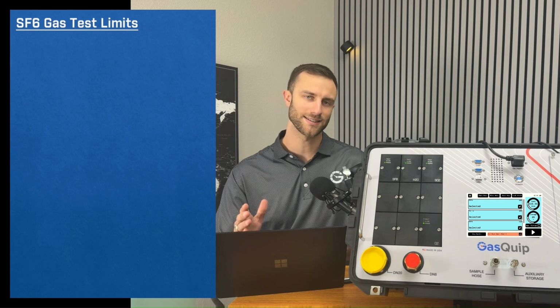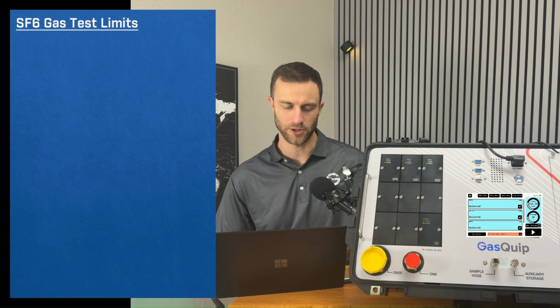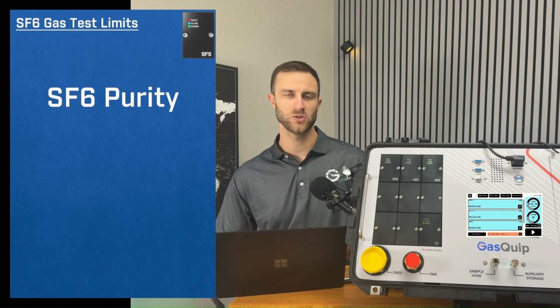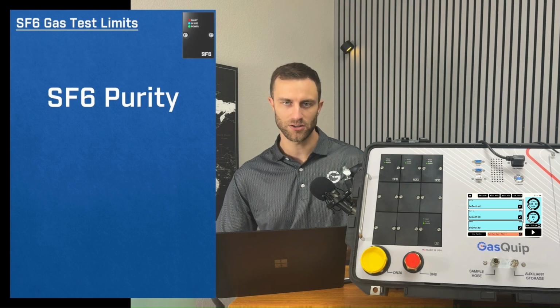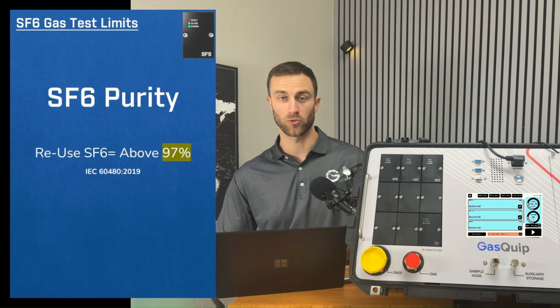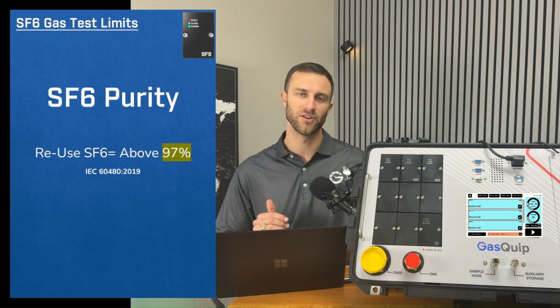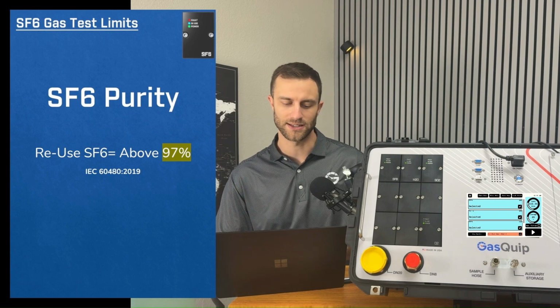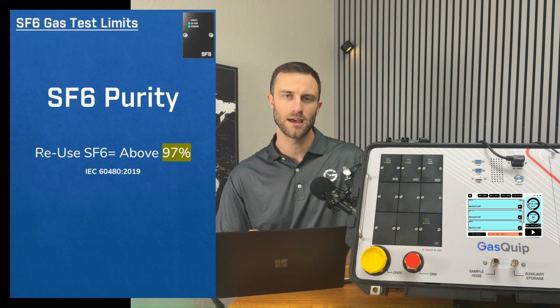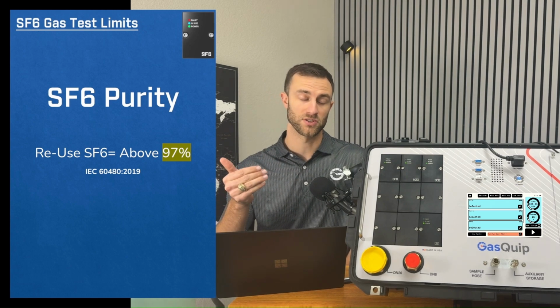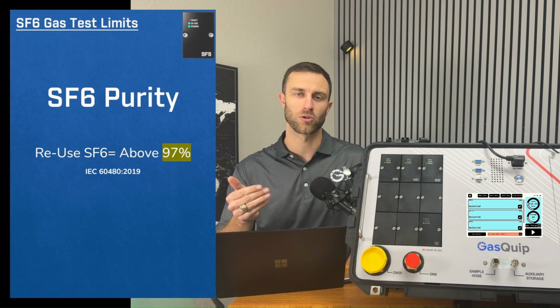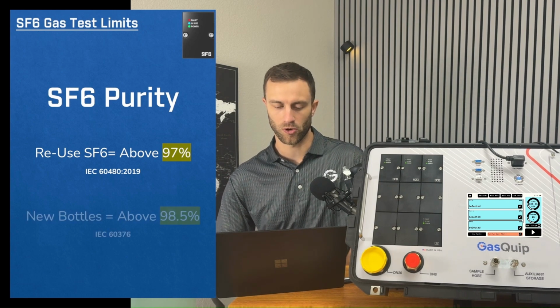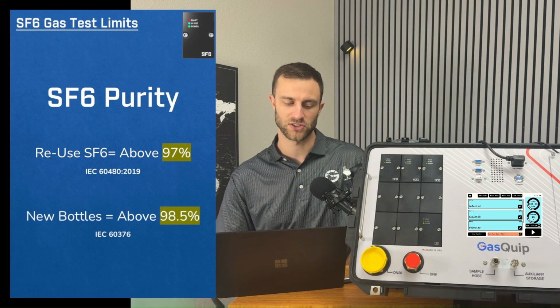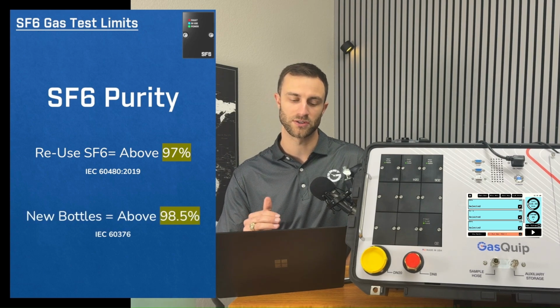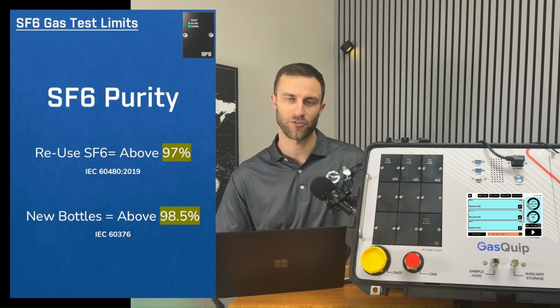Let's talk test limits and start with SF6 gas purity. For SF6, we've got two test limits that we'll talk about from the IEC recommendations. The first one, for reuse SF6, you have to be above 97%. That's from the IEC 60480. Now, reuse is defined as reclaimed gas that's going to be reused either in the same gas insulated equipment or different equipment. So for new bottles or virgin SF6, the percent threshold that IEC sets is 98.5%.